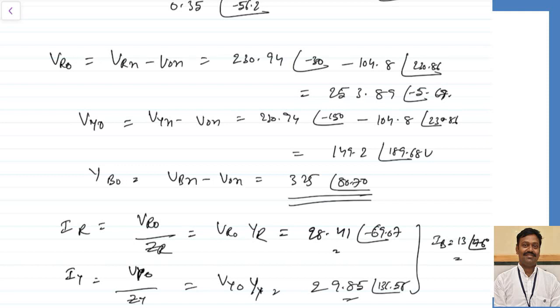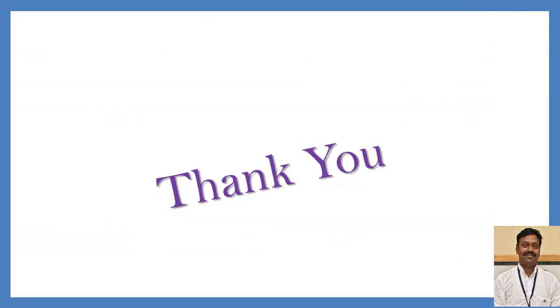This concept is called the shifting neutral concept in a star connection. To avoid neutral shifting, the only option is to connect the two neutrals together. In our households, the neutral point is always available and connected to the neutral of the transformer — because the three phases are not loaded in a balanced way, different phases would get different voltages and equipment could be damaged. Always connect the neutral point. I hope the star connection is completely clear. If you have any queries, leave your comments in the comment section below. Thank you very much.